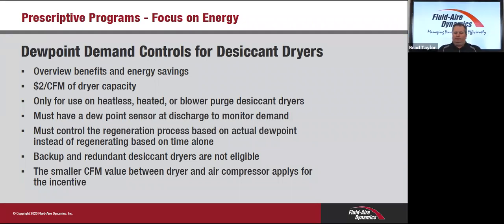Okay, very good. So when you're considering 15% purge, if we go back and use that number of $35 per CFM that I was referring to earlier, take a 100 CFM system for round numbers, 15 CFM of that is just going to the purge system. Well, if I could drop that by 50%, multiply that 15 times $35, multiply it by 0.5, it computes out to a couple thousand dollars a year. That's just a small system, okay? You can buy retrofit dew point demand controllers for around $5,000. So it's a very, very fast ROI when we're talking about these types of controls.